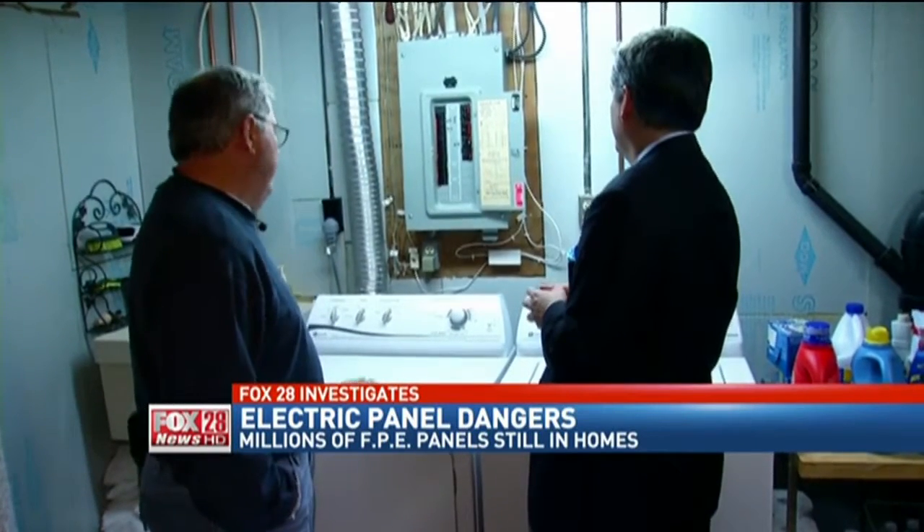As for Roy Jaycox, he says it's time to do what he should have done two years ago: get that box replaced. This is serious — some banks won't give you a mortgage if you have one of these panels, and most insurance companies won't insure your home either. What you need to look for: 'Federal Pacific' on the box, and the signature red strips on the breakers themselves — that's the big clue you've got one of these Federal Pacific Stab-Lok panels. People usually don't realize they have it until there's a problem, but thankfully in my case we caught it and got it out of there. Let's all go check those panels.